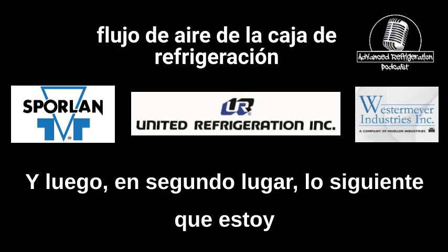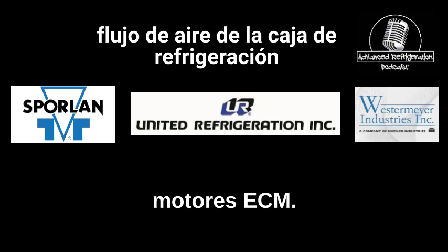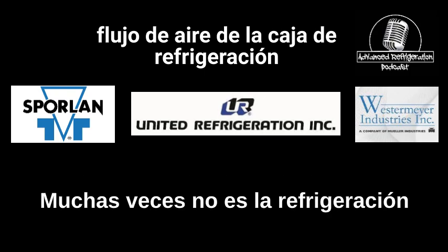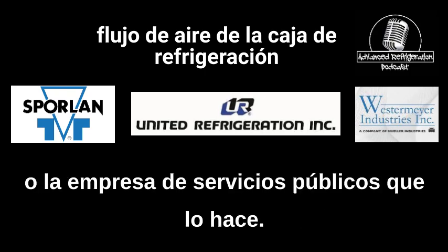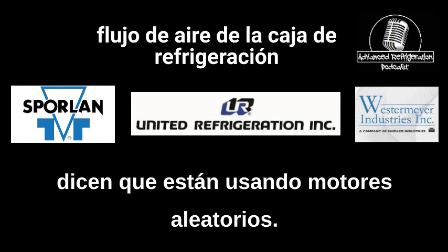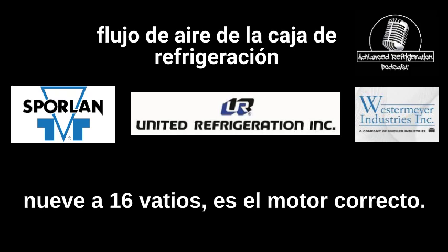Second, the next thing I want to go into is fan motors. ECM motors. A lot of these ECM retrofits are coming through, with energy companies retrofitting these motors. A lot of times it's not the refrigeration vendor doing it. It's an energy management company or the utility company. Obviously they're not looking at every motor. They're ordering bulk motors and using random motors. Not every ECM motor, even though it says it's 9 to 16 watts, is the correct motor.